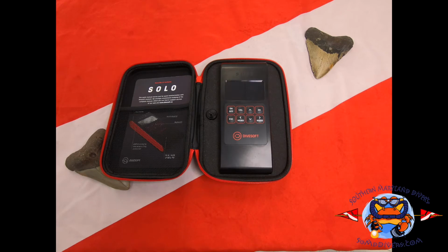Where the tech really gets interesting is that the helium sensor in here is solid state. And when I say solid state, that means it will never ever need to be replaced. There are no other Trimix analyzers on the market right now that I'm aware of that have that technology. For instance, there's another one that we use where the helium sensor would need to be replaced. Now, helium sensors generally last a fairly good amount of time longer than an oxygen sensor. However, this one will never need to be replaced, and the technology behind that's really cool. It actually measures the speed of sound between two different microphones in there to tell you the mix that's in there for the helium portion of it.